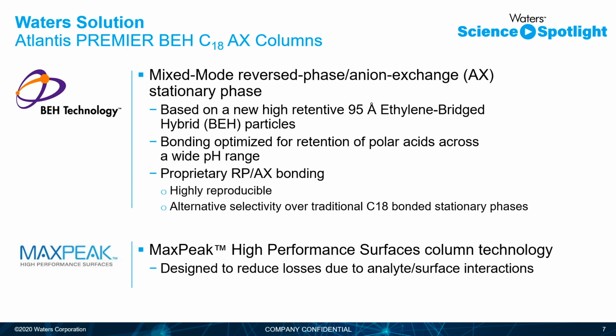So Waters' solution was to create its own reverse phase anion exchange column, the Atlantis Premier BEH C18 AX column. It's a mixed mode reverse phase anion exchange stationary phase. It's based on a new highly retentive 95 angstrom ethylene bridged hybrid particle. The surface bonding is optimized for the retention of polar acids across a wide pH range. It has a proprietary reverse phase anion exchange bonding, which is highly reproducible and provides an alternative selectivity to traditional C18 bonded stationary phases. We've also implemented a new technology in the hardware, MaxPeak High Performance Surfaces.